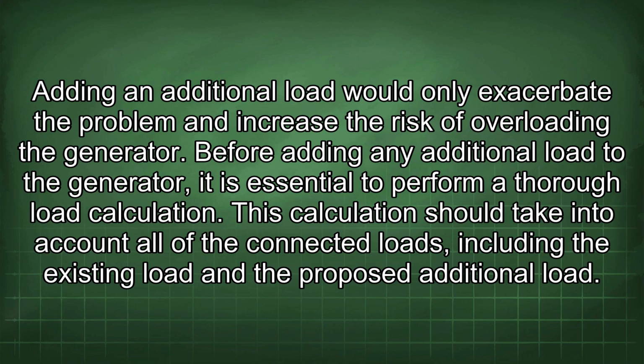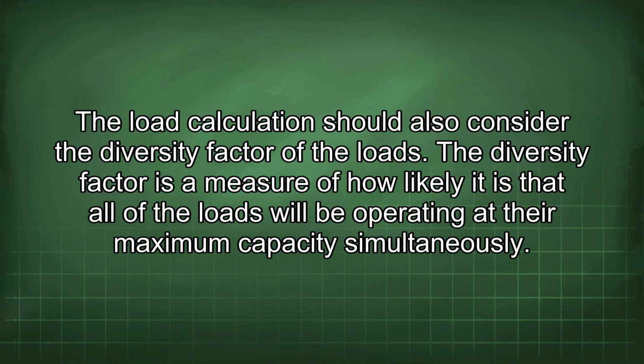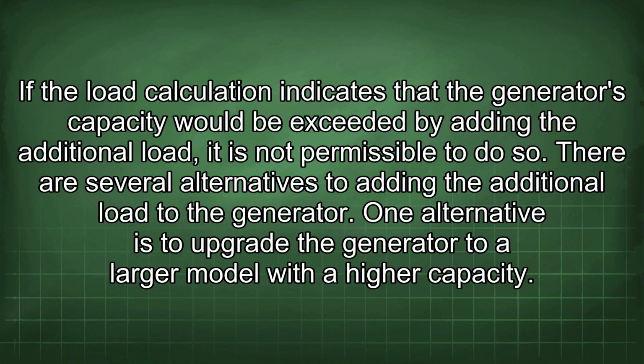Before adding any additional load to the generator, it is essential to perform a thorough load calculation. This calculation should take into account all of the connected loads, including the existing load and the proposed additional load. The load calculation should also consider the diversity factor of the loads. The diversity factor is a measure of how likely it is that all of the loads will be operating at their maximum capacity simultaneously. If the load calculation indicates that the generator's capacity would be exceeded by adding the additional load, it is not permissible to do so.